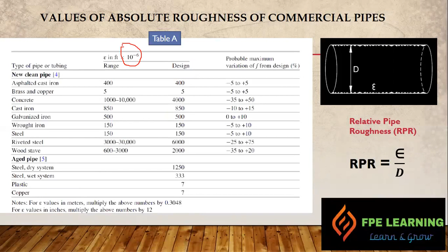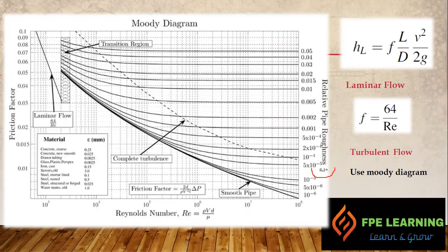So to find the relative pipe roughness, which is epsilon E over D, just use the formula. If you use E from the data sheet or from this table, let's say we have 500 at this location. So it's not 500, it is 500 into 10 to the power minus 6, because we have to multiply by 10 to the power minus 6, and now we come into feet, and then take the diameter in feet. We got some RPR values. Directly from those RPR values, go to these levels, find the Reynolds number, and go to the friction factor. We have done, right? So this is all about the Moody diagram.